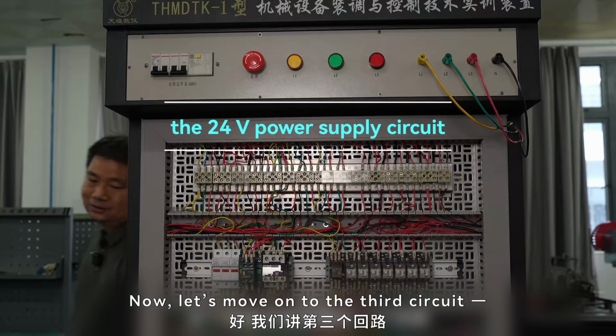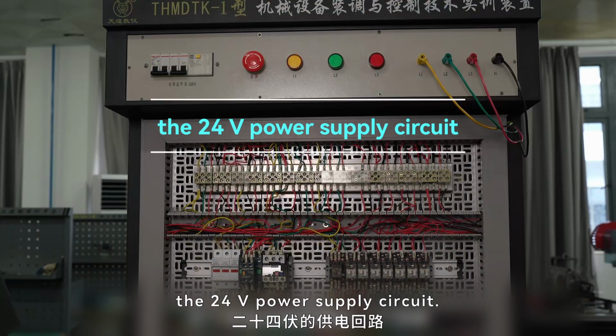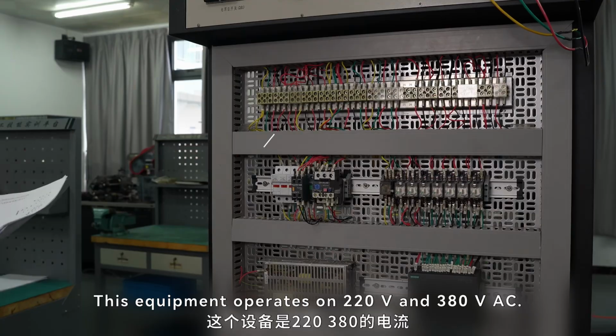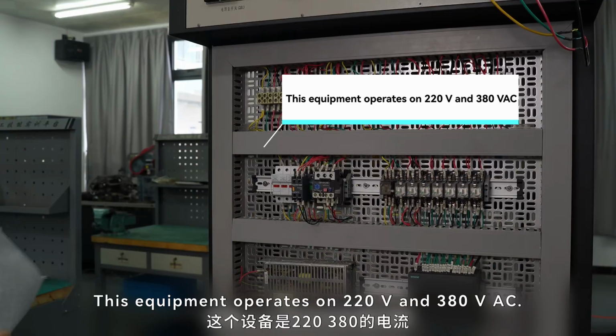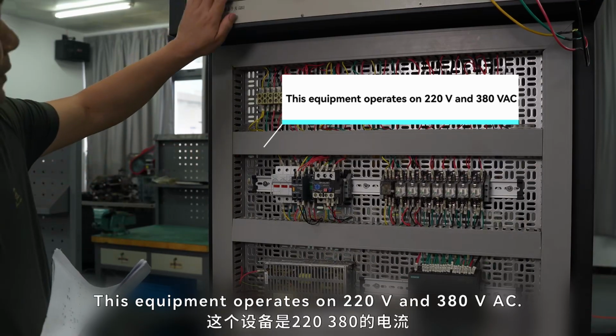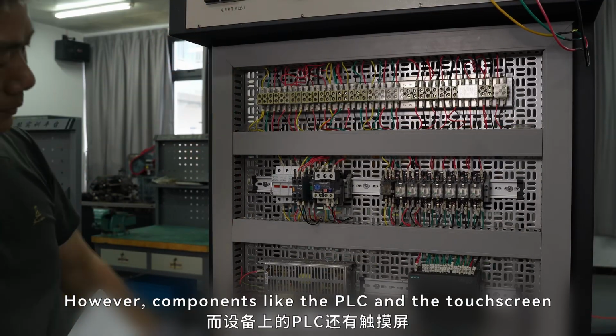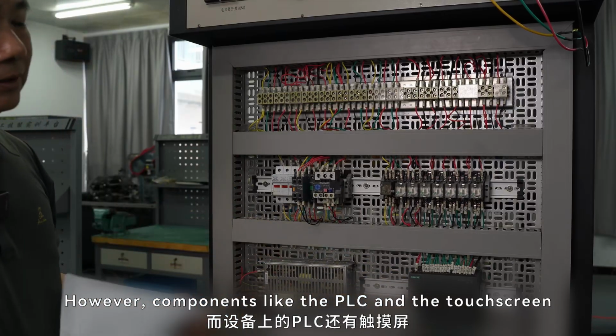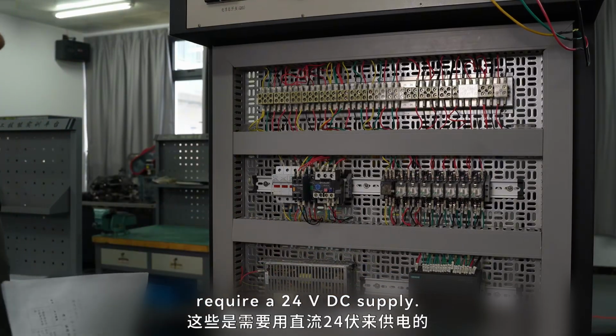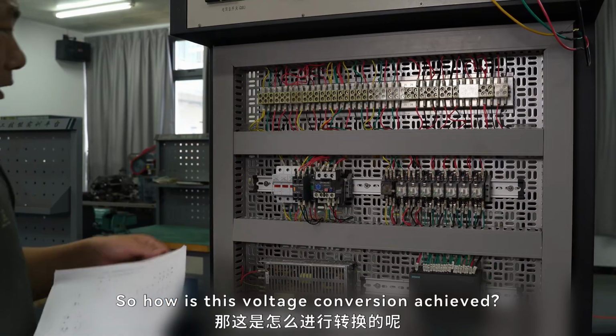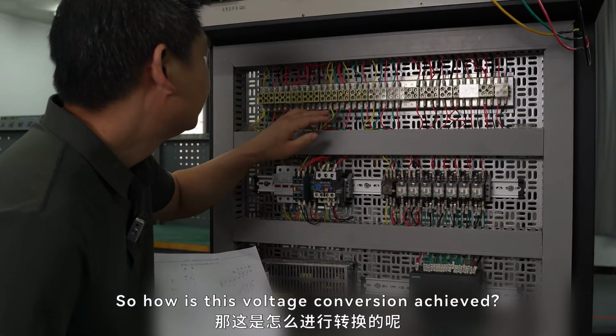Now, let's move on to the third circuit, the 24 volts power supply circuit. This equipment operates on 220 volts and 380 volts AC. However, components like the PLC and the touchscreen require a 24 volts DC supply. So how is this voltage conversion achieved?